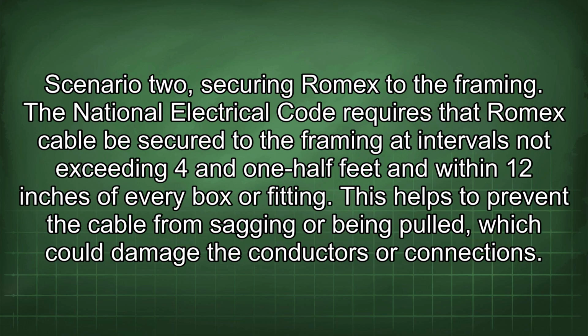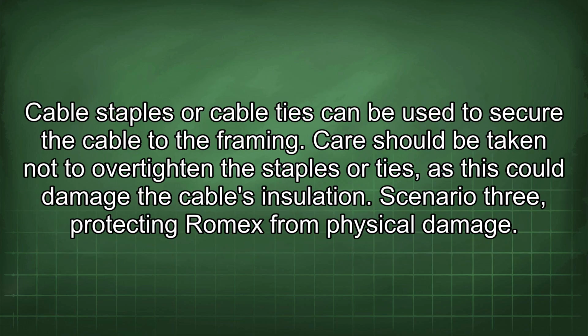Scenario 2. Securing Romex to the framing. The National Electrical Code requires that Romex cable be secured to the framing at intervals not exceeding 4½ feet and within 12 inches of every box or fitting. This helps to prevent the cable from sagging or being pulled, which could damage the conductors or connections. Cable staples or cable ties can be used to secure the cable to the framing. Care should be taken not to over-tighten the staples or ties, as this could damage the cable's insulation.